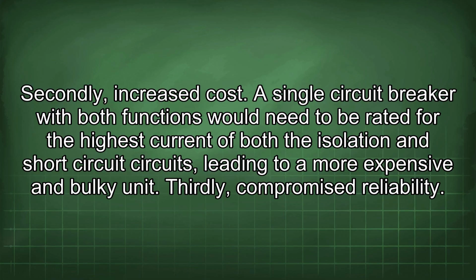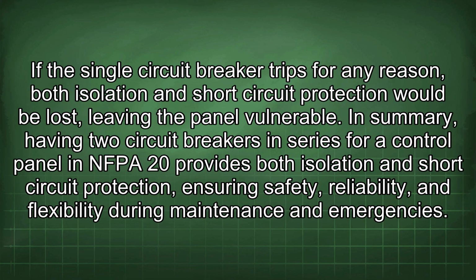Thirdly, compromised reliability. If the single circuit breaker trips for any reason, both isolation and short circuit protection would be lost, leaving the panel vulnerable. In summary, having two circuit breakers in series for a control panel in NFPA 20 provides both isolation and short circuit protection, ensuring safety, reliability, and flexibility during maintenance and emergencies.